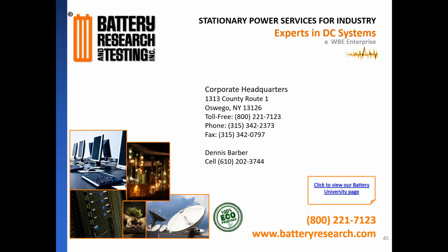But if a plant or an application is calling for a 600 ampere hour reserve, we'll recommend 300 ampere hour, or usually bump it up a little bit higher, 350, whatever, in parallel systems, so that one can be taken out of service without having to bring in a temp. You don't always have that luxury. So now you can take one off and do some troubleshooting.